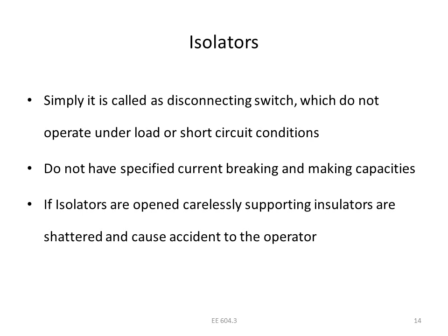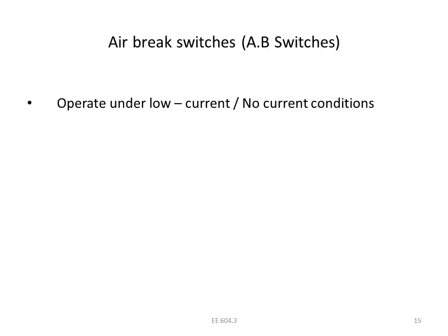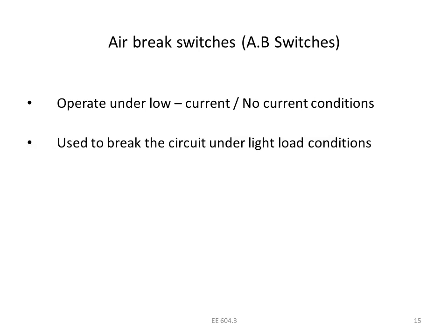If isolators are opened under load, the supporting insulators can be damaged and the equipment will be damaged. They should be opened only at no load conditions. Coming to the AB switch, that is the air break switch, it is operated under low current. It is used to break under light load conditions and is operated manually.